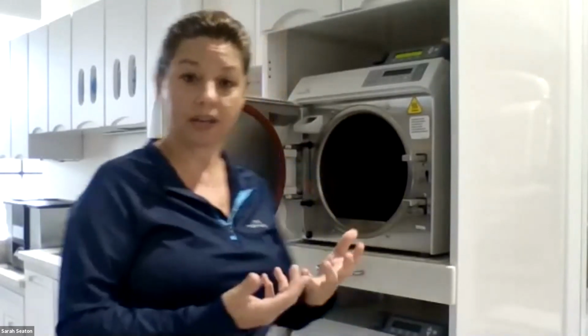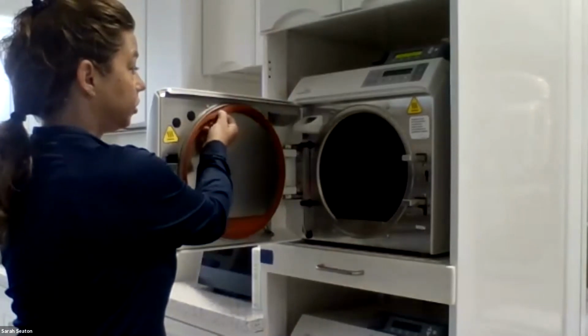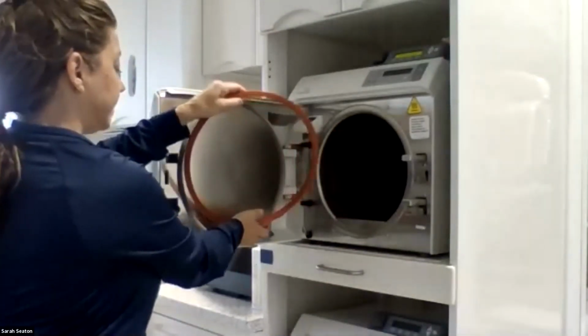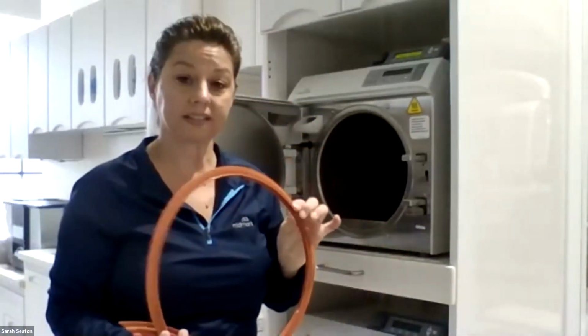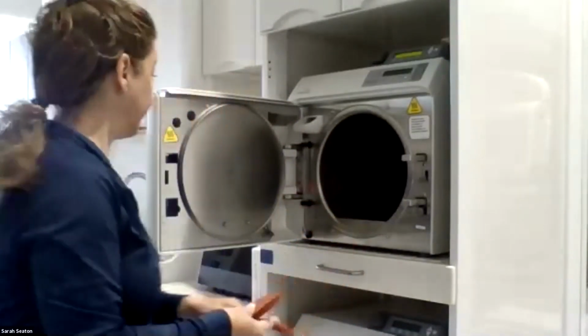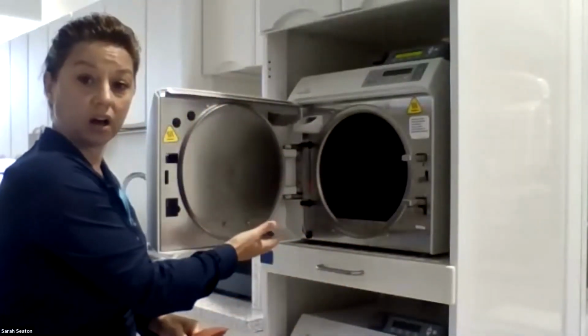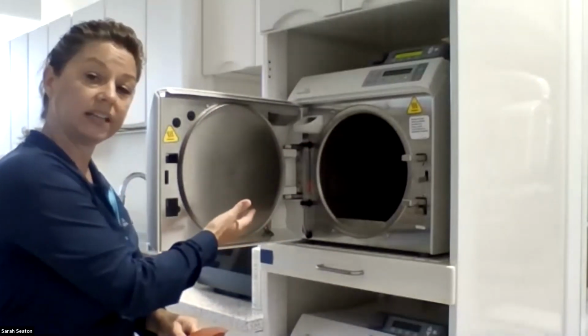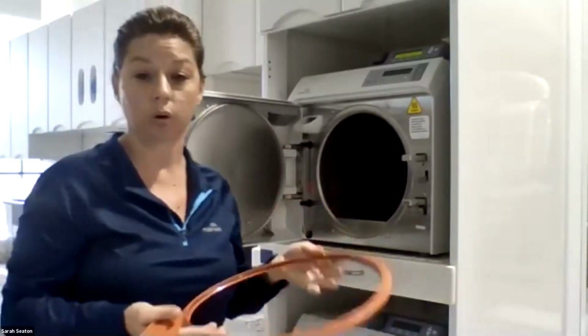So the next step in the monthly maintenance is the door gasket. You want to take that out. You want to wipe this down, clean it, clean the internal surfaces of your door gasket housing, look for any damage or wear.